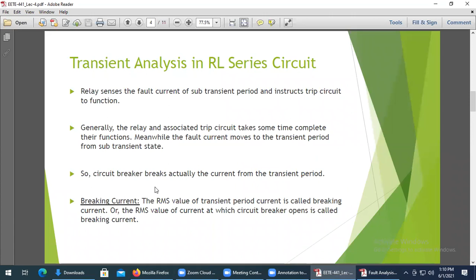As we are dealing only with protective devices, the analysis part is normally omitted in this course. But without proper analysis of the fault, you cannot protect a power system, because what should be the rating of the circuit breaker, the breaking capacity, the making capacity - all these things actually come from the analysis of a particular system.